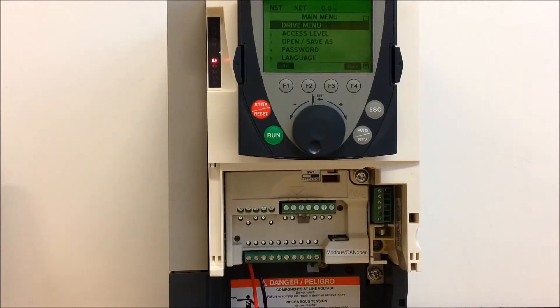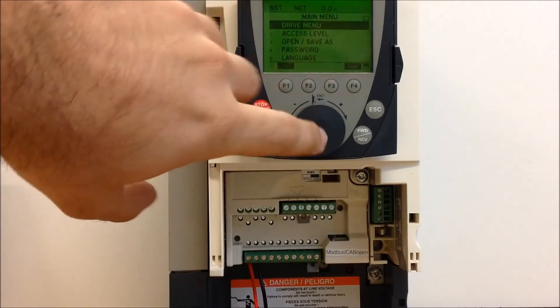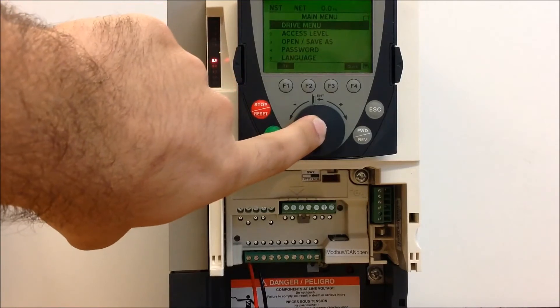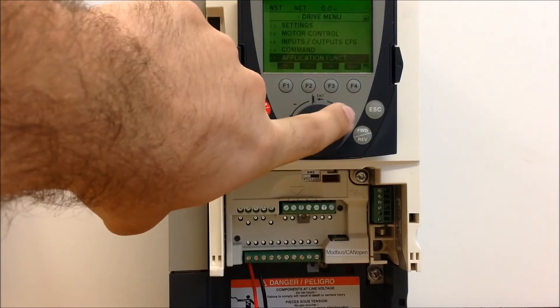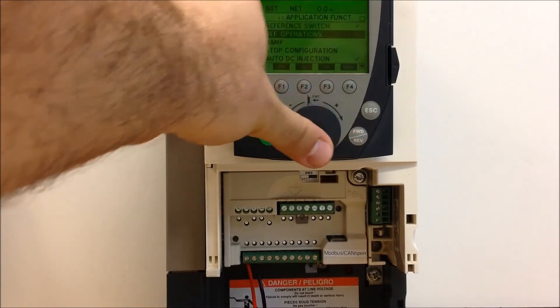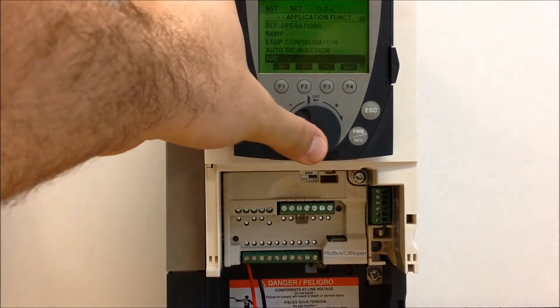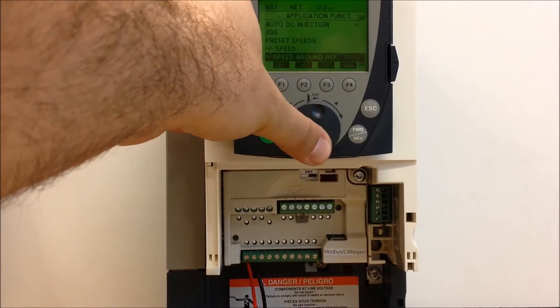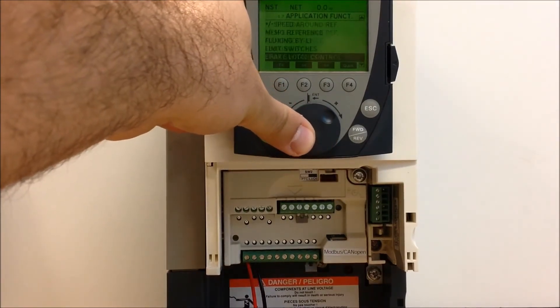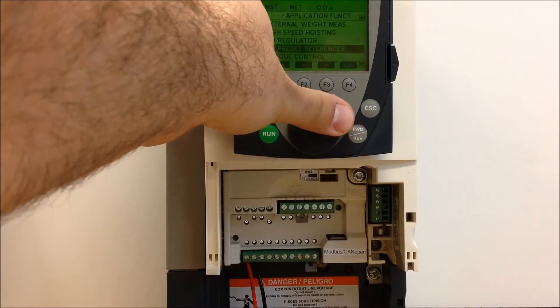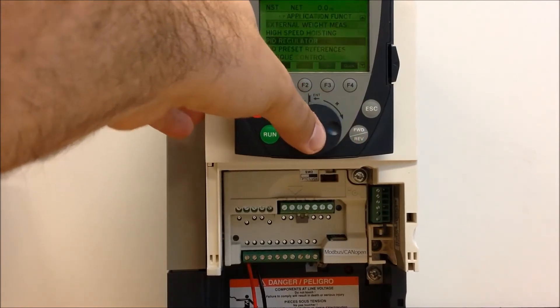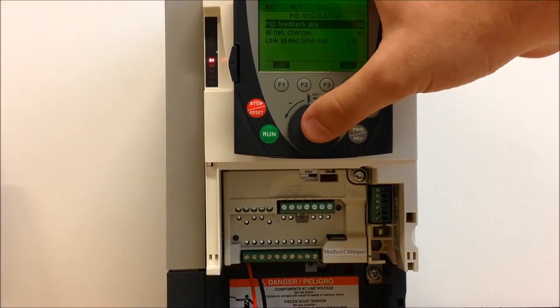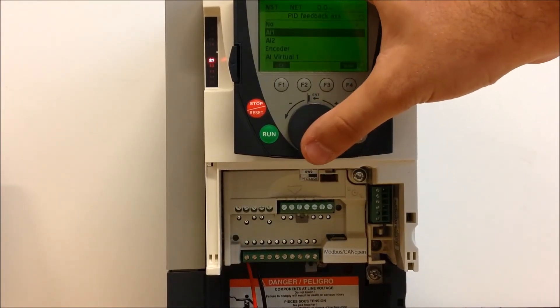First of all, let's go into your PID menu. To do that, go from your main menu to your drive menu, go to 1.7 application function, go down to PID regulator. Alright, so once you're in here, right now we have the function turned off. Let's just go ahead and turn it on as an example here.